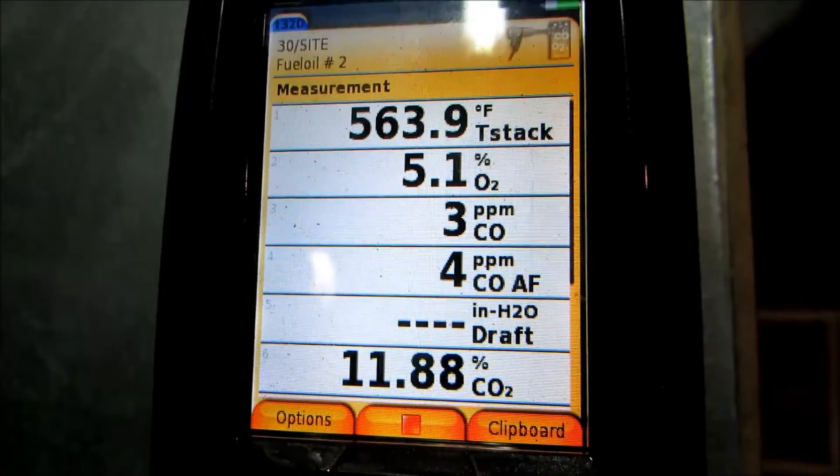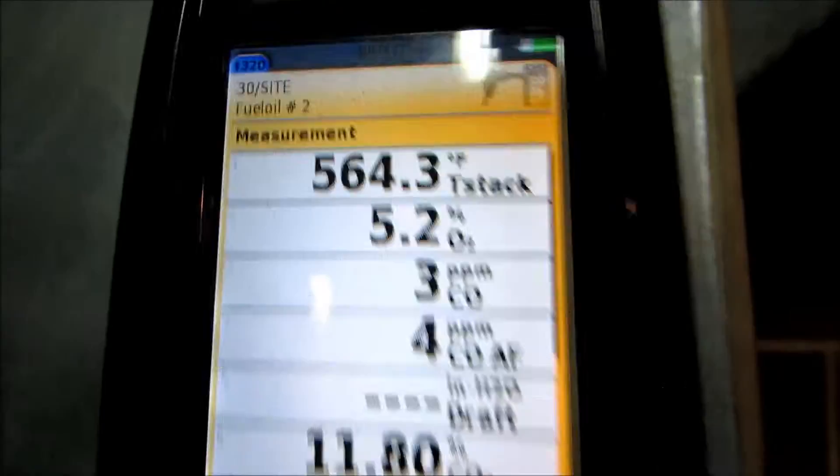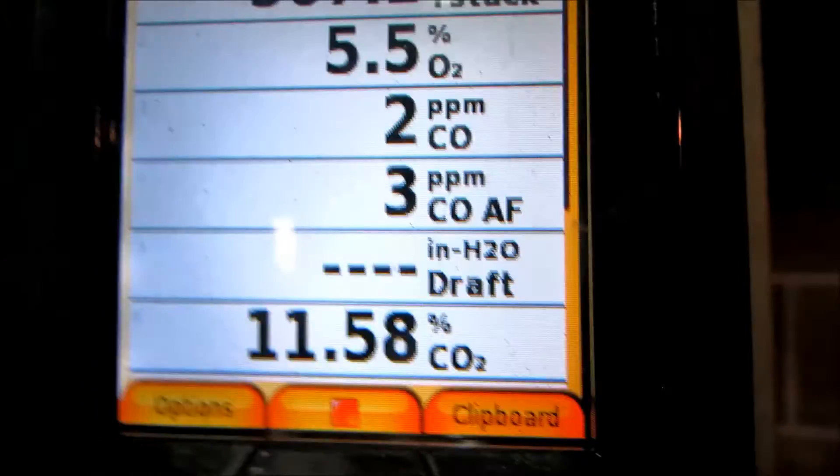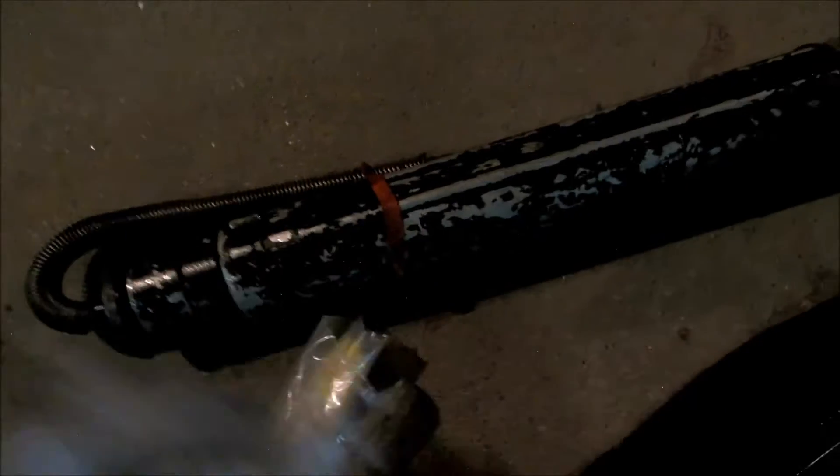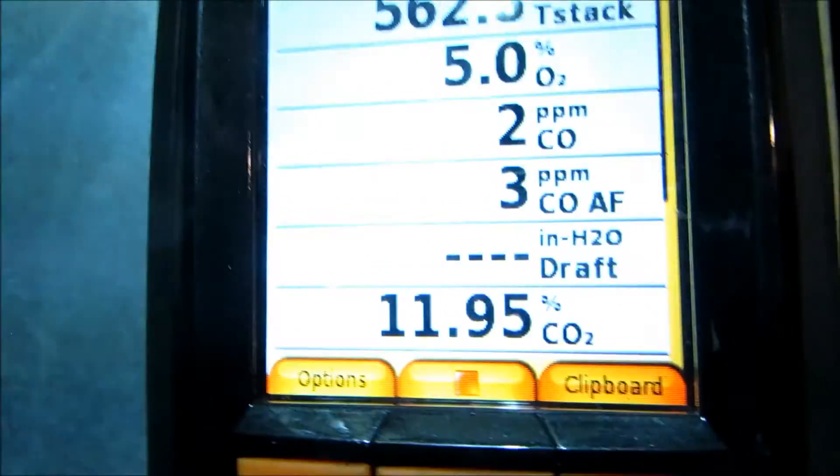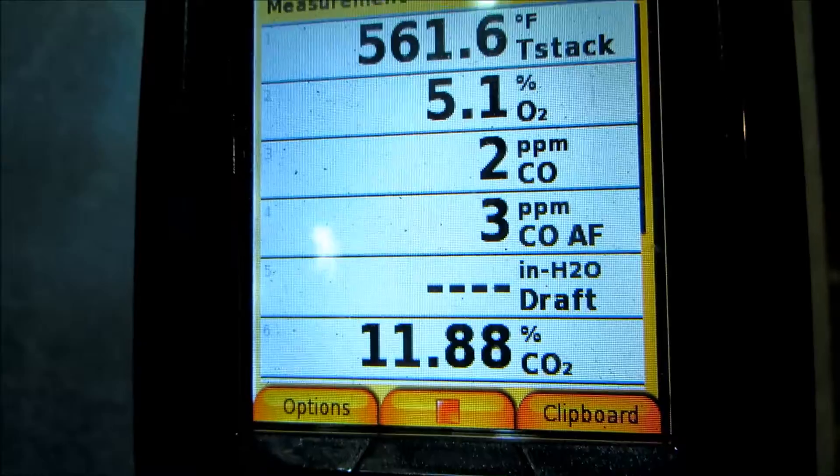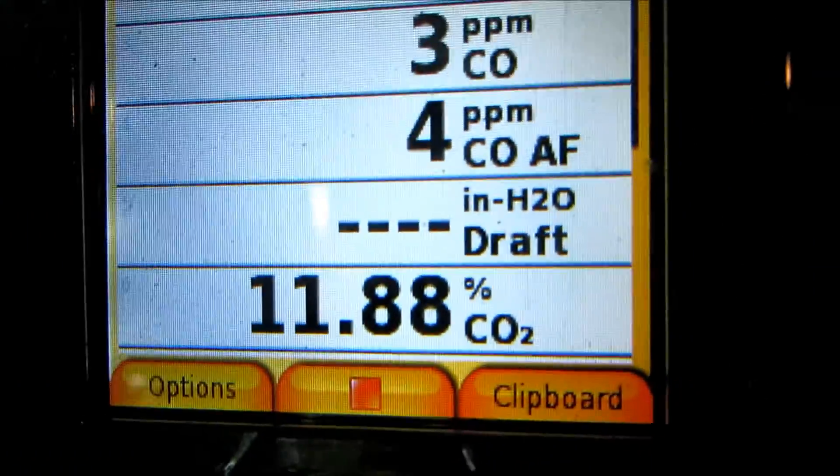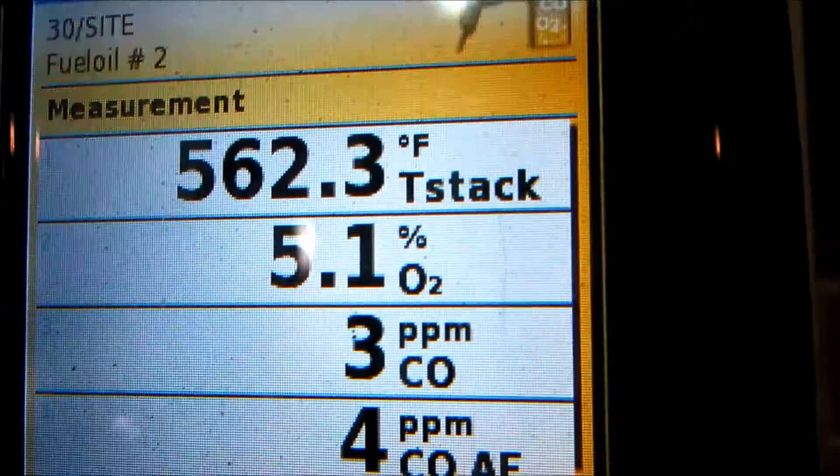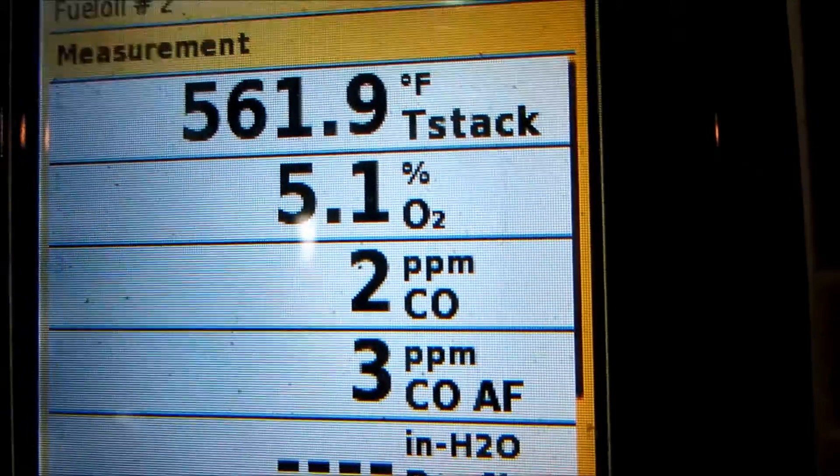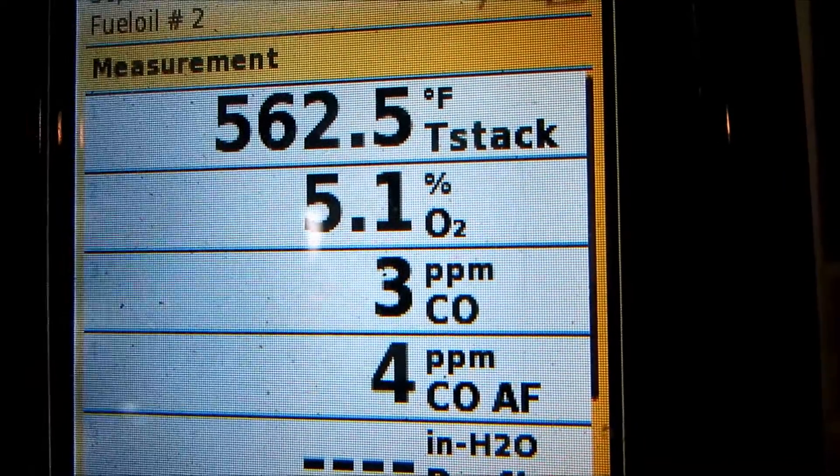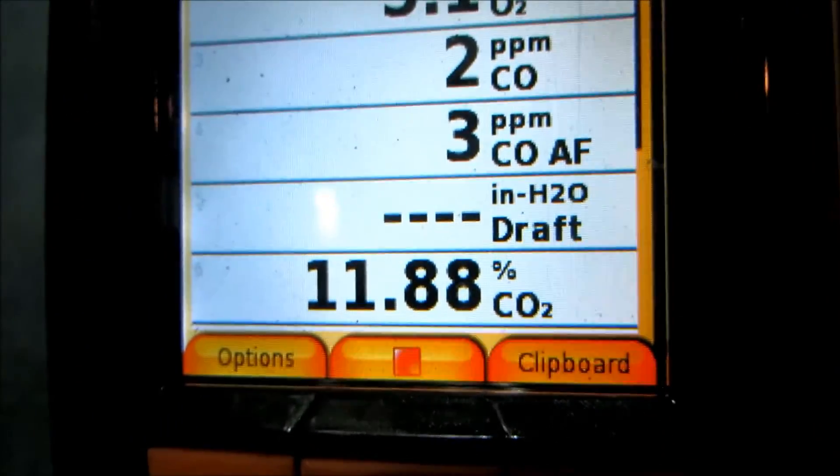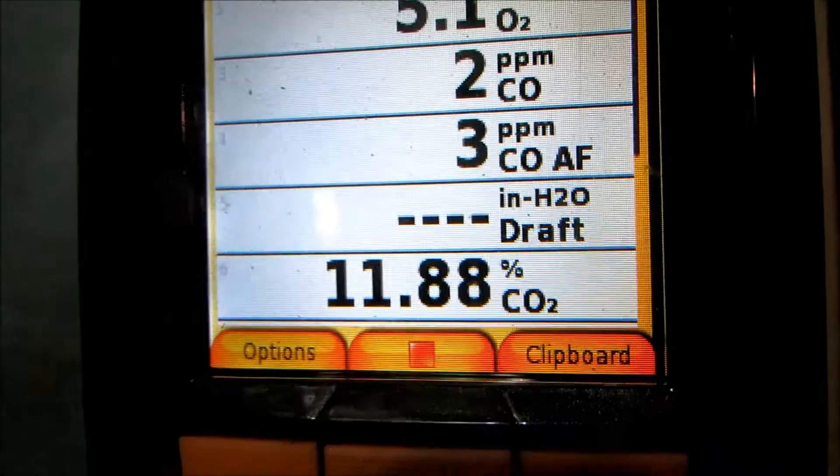Can't beat the Testo, can't beat the Testo 320. Draft gauge if I want to check the draft. A little smoke paper - should put a little paper in this thing, pump it 10 times in the smoke pipe, see if it's going to smoke. Alright, I'm good, I'm just below 12 there. Now with the CO2, I'm good with that. We'll check it for smoke. Parts per million, we're good there. We'll check it for smoke.